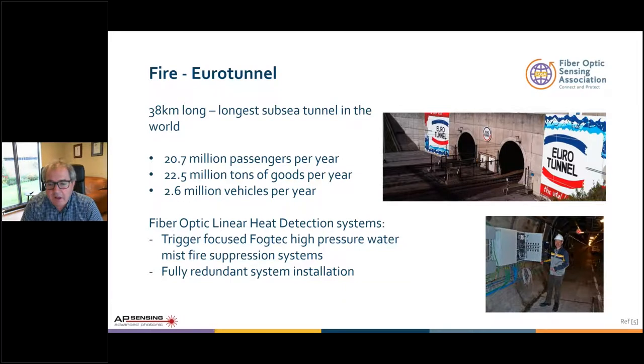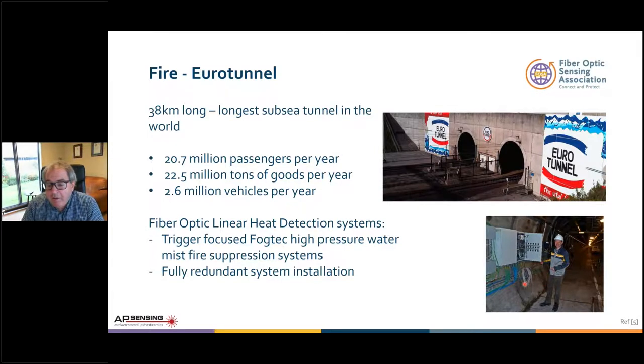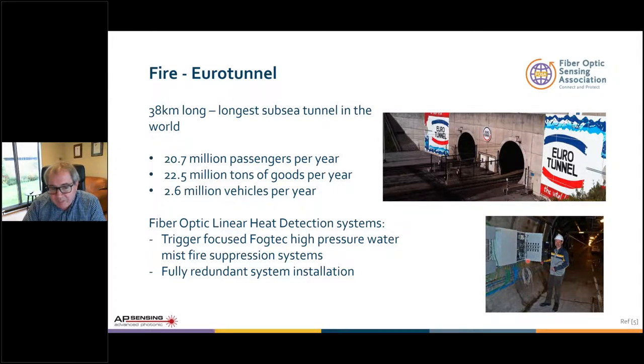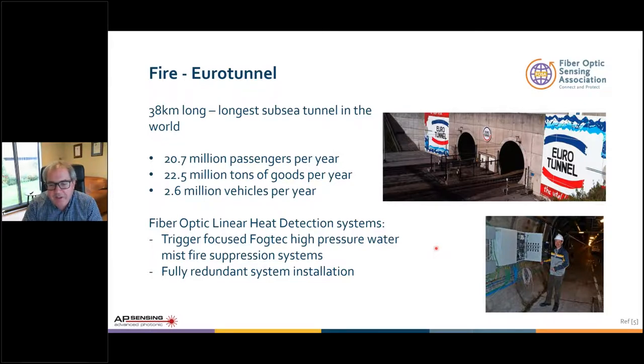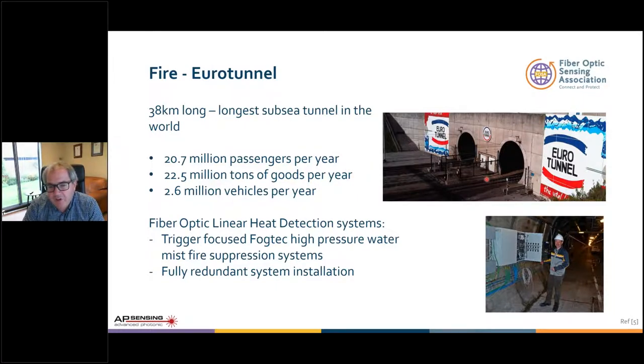Another tunnel case is the Eurotunnel — 20 million passengers per year — also protected by fiber optic linear heat detection systems installed in cabinets along the wall. The linear heat detection systems activate the high-pressure water fire suppression systems. If a fire breaks out in any area, the fire suppression system is automatically activated. In this tunnel with electric trains, the immunity to electrical signals makes fiber optics perfect. The false alarm rate is incredibly low for fiber optic sensors.